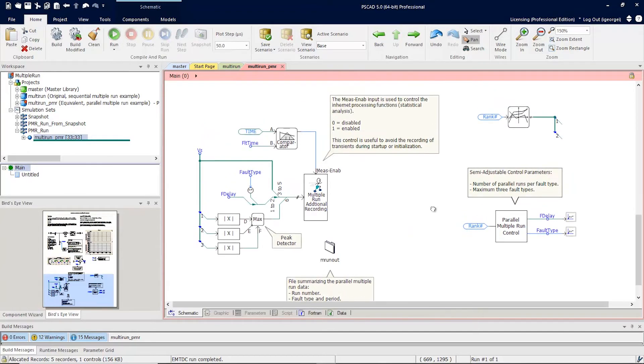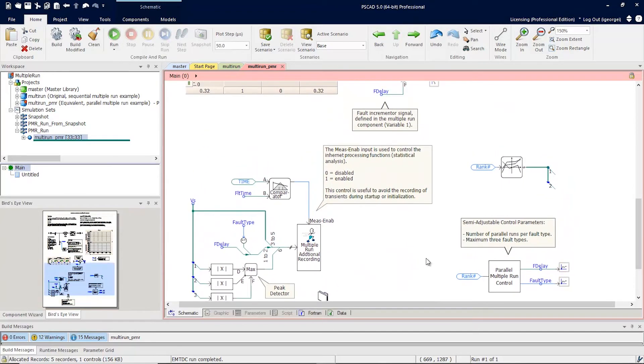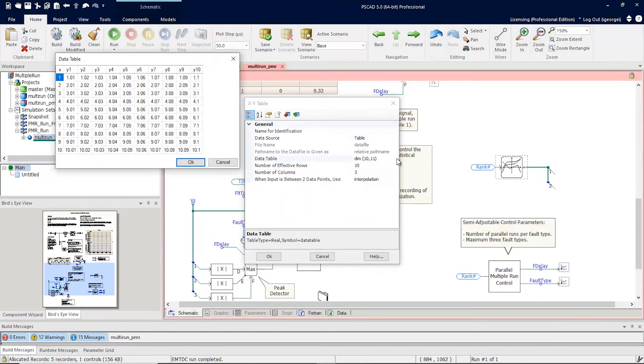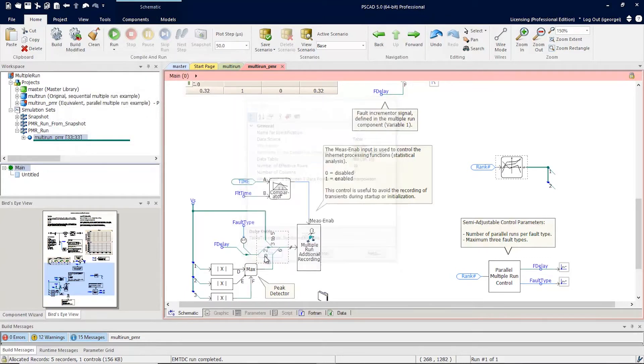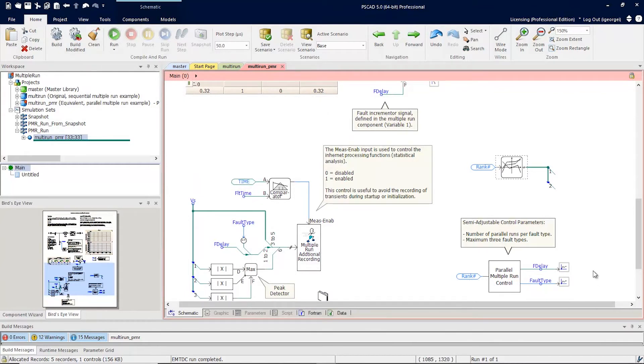Another way of doing this is to use a table. The rank number is simply fed into this table. And in the table, you can define the different values used for fault time and fault type. In this example, you would then just take the fault delay and fault type signals here and attach them to the outputs here.